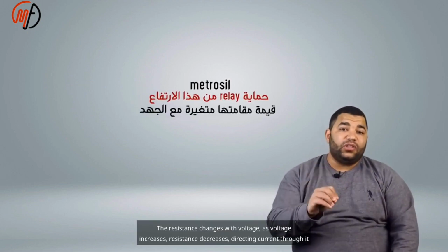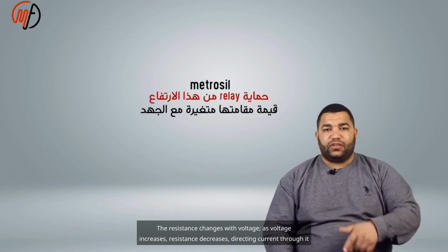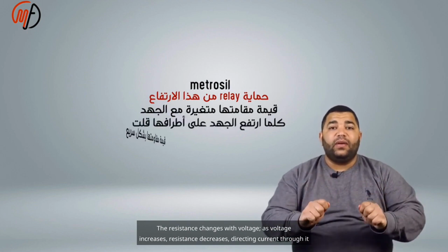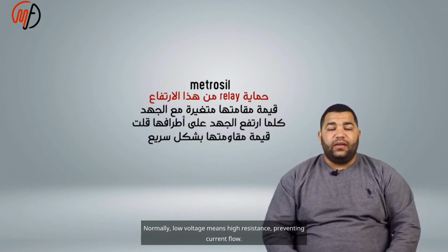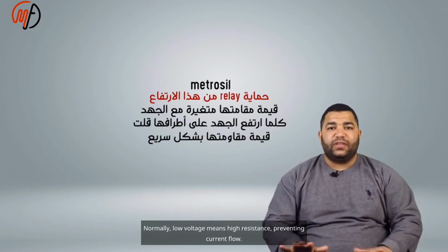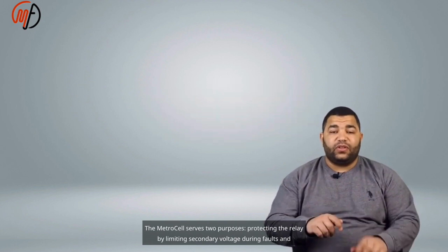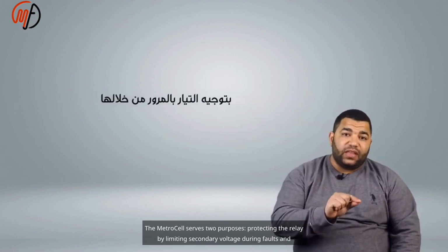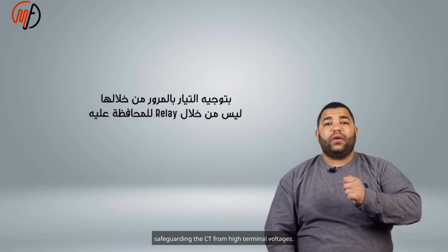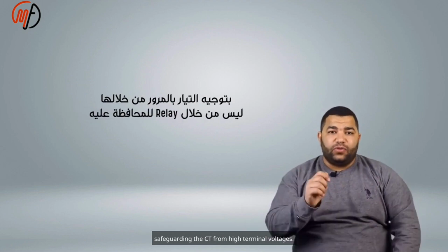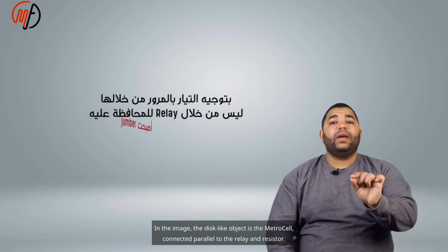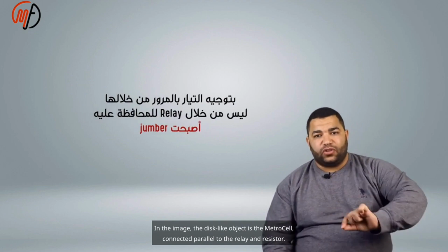The resistance changes with voltage. As voltage increases, resistance decreases, directing current through it instead of the relay during spikes. Normally, low voltage means high resistance, preventing current flow. The Metrosil serves two purposes: protecting the relay by limiting secondary voltage during faults and safeguarding the CT from high terminal voltages. In the image, the disc-like object is the Metrosil, connected parallel to the relay and resistor.